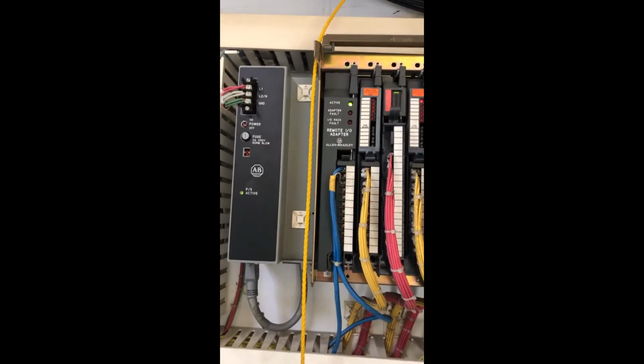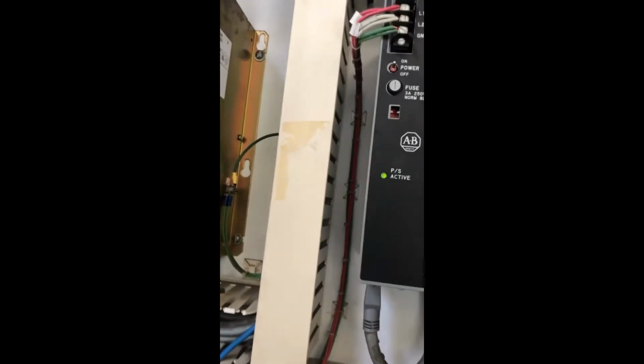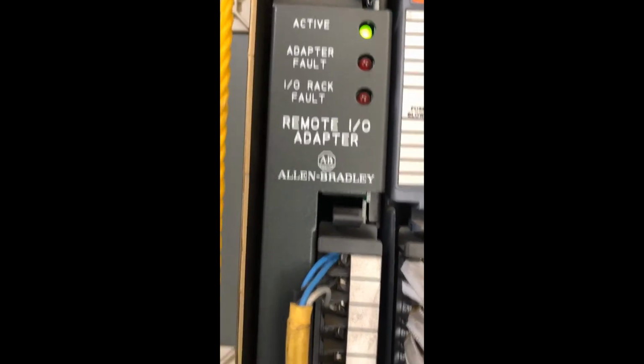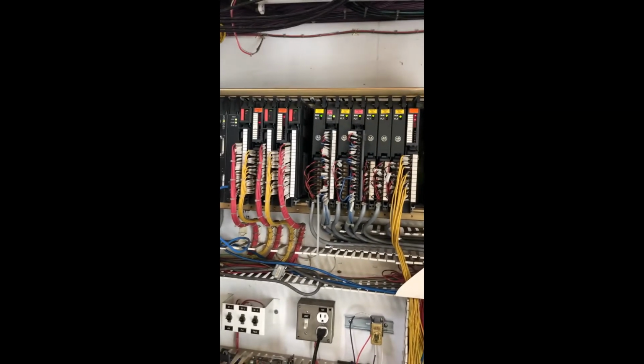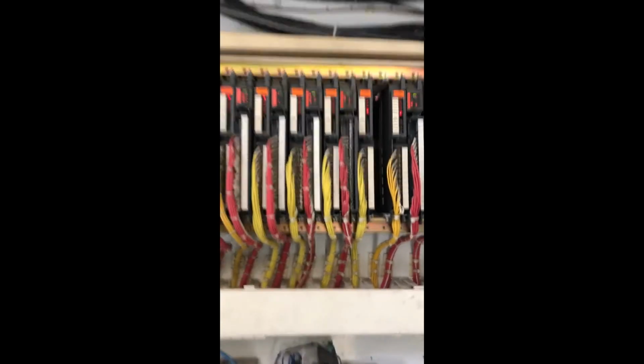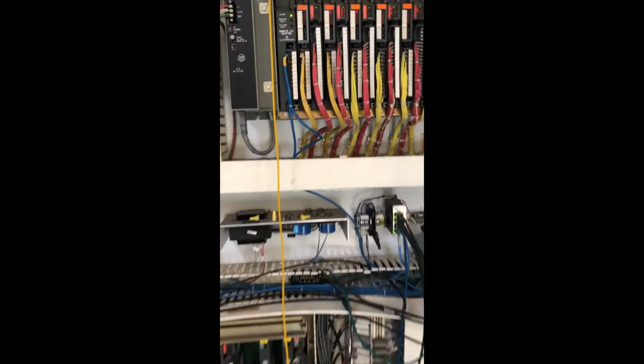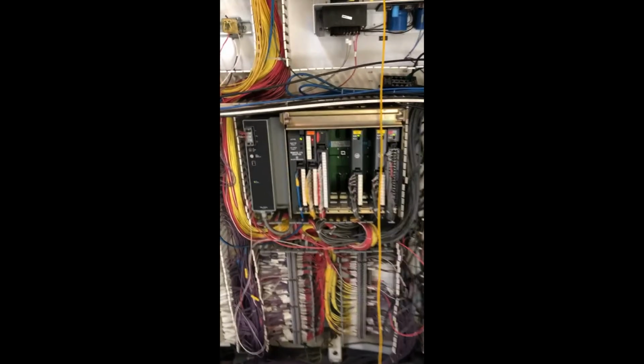And then over here it's the same thing. This is just an extended I/O rack. This cable right here, this remote I/O adapter, it simply goes over to the main and connects right here. And all it does, it just makes this first rack bigger, so to speak. Okay, so it's just extending and giving us significantly more I/O. This particular PLC cabinet has two extended I/O racks. There's one here, and there's one right below.